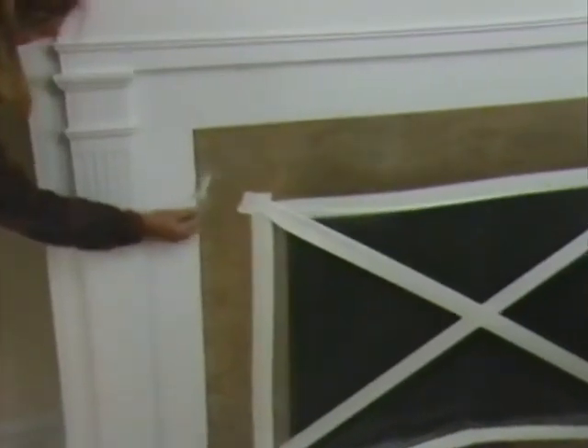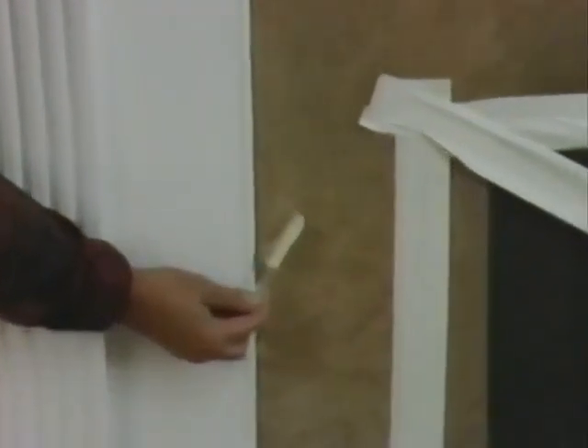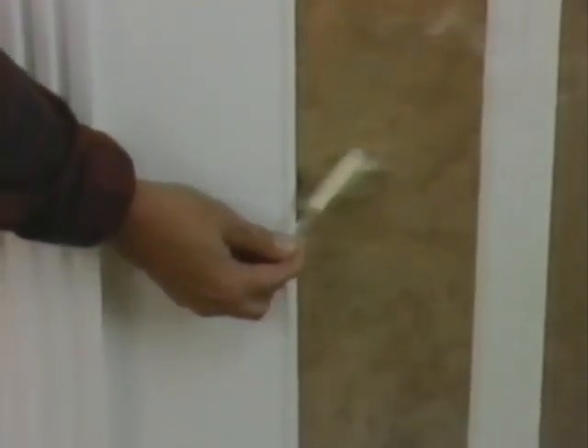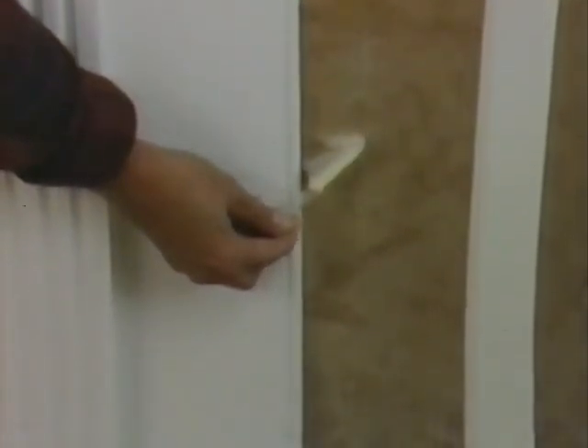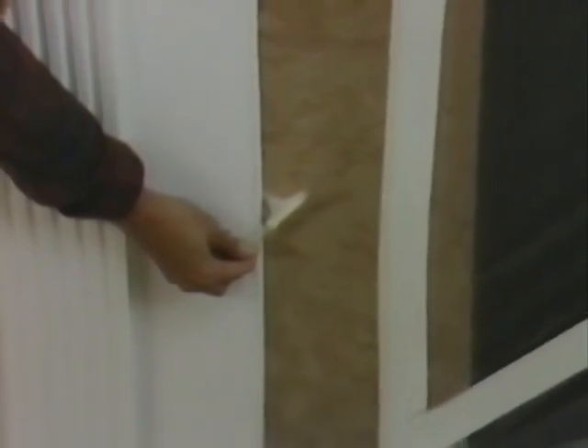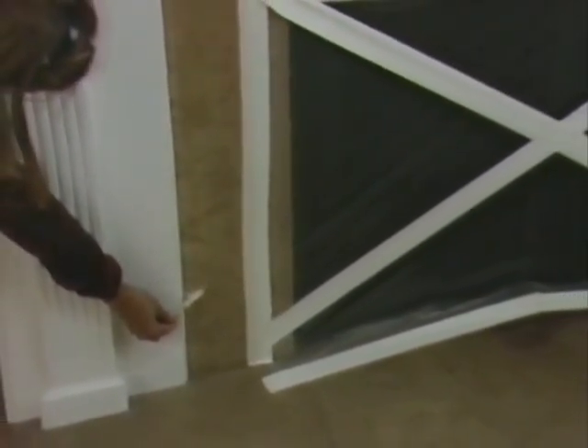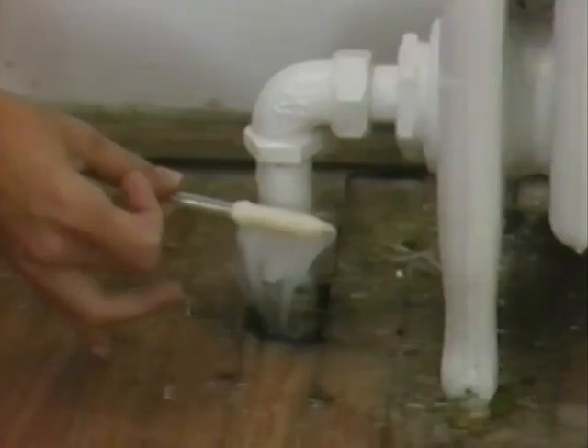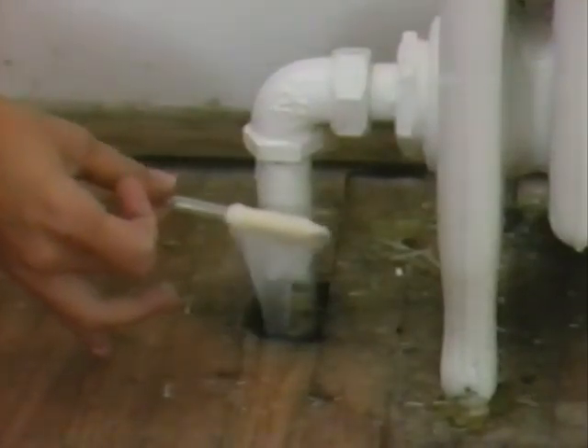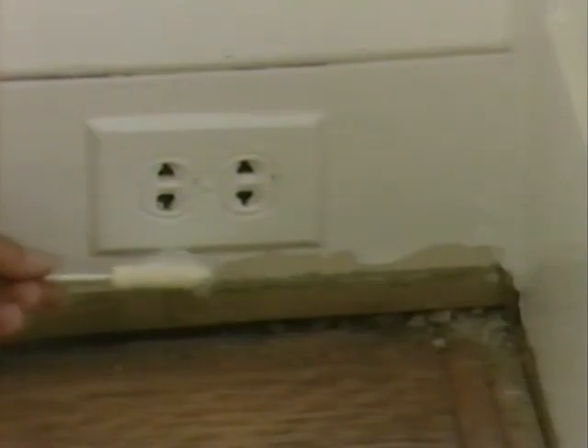Right now, the house is being pressurized and the smoke shows where the heat leaks out. As we can see, the edges of the fireplace are a place where warm air can escape. The fireplace itself needs to be sealed with plastic for the test. It loses so much heat that it would throw off the rest of our test. We'll deal with that opening later. Holes in the floor where radiator pipes enter are also places that can lose heat. Baseboards are another.